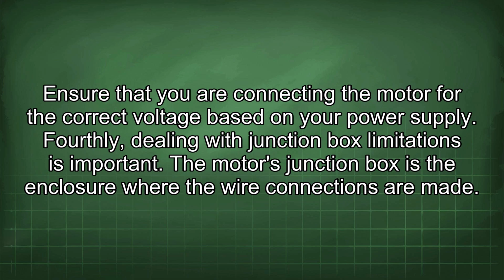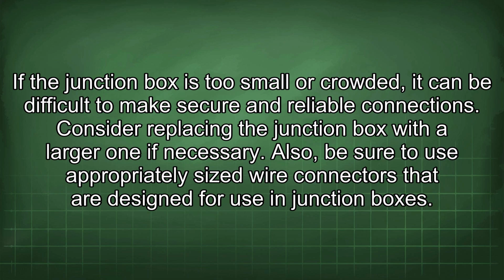Fourthly, dealing with junction box limitations is important. The motor's junction box is the enclosure where the wire connections are made. If the junction box is too small or crowded, it can be difficult to make secure and reliable connections. Consider replacing the junction box with a larger one if necessary. Also, be sure to use appropriately sized wire connectors that are designed for use in junction boxes.